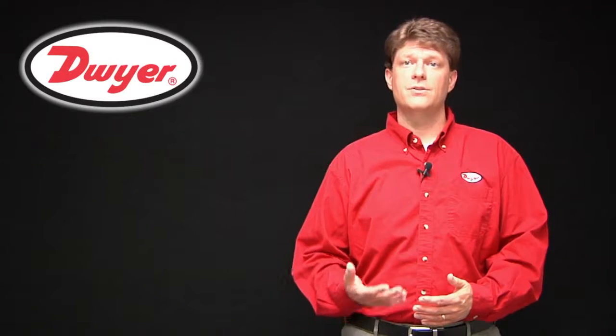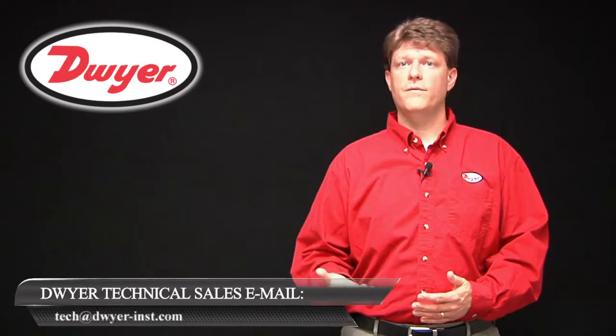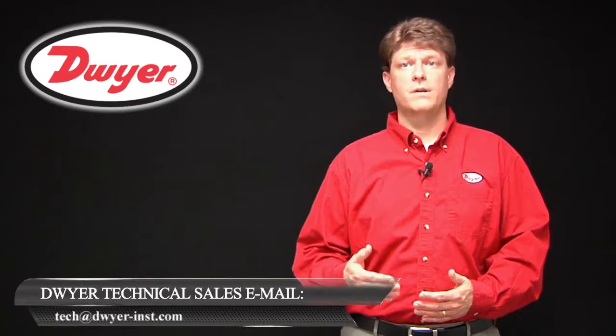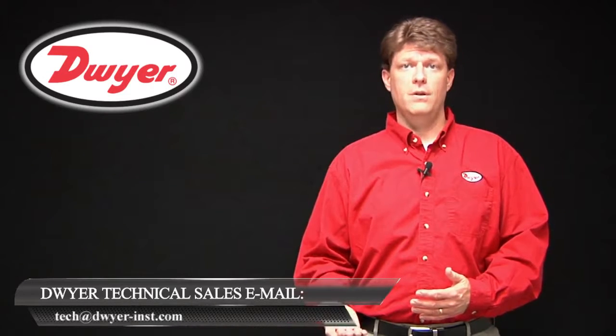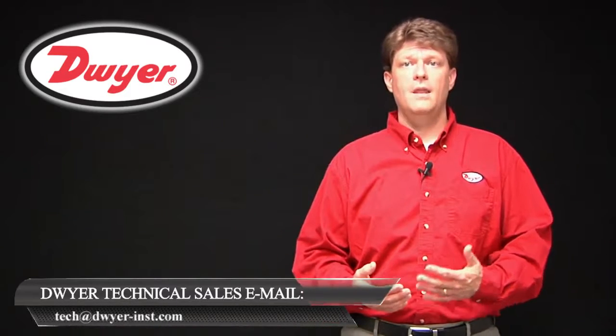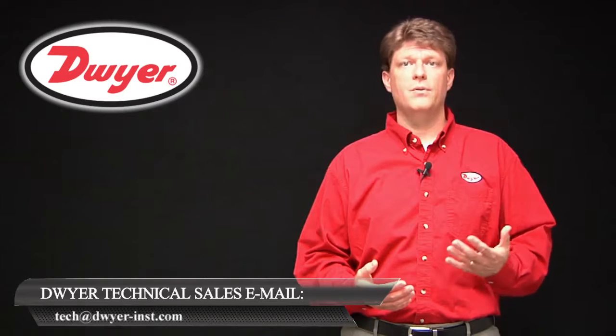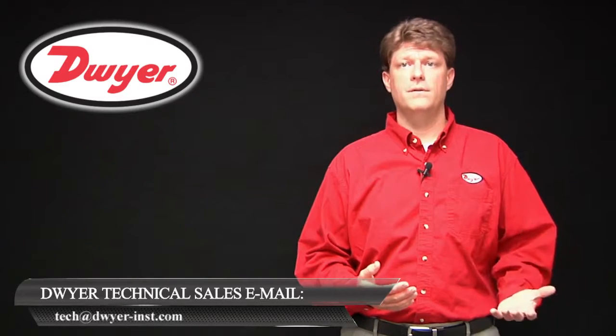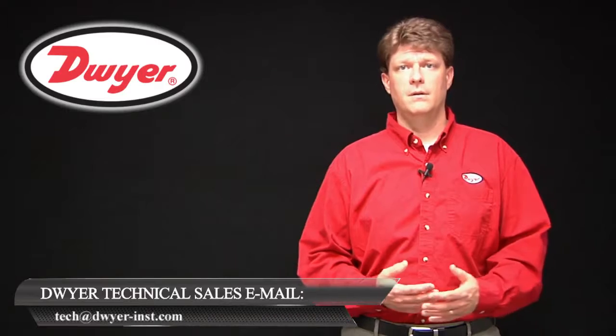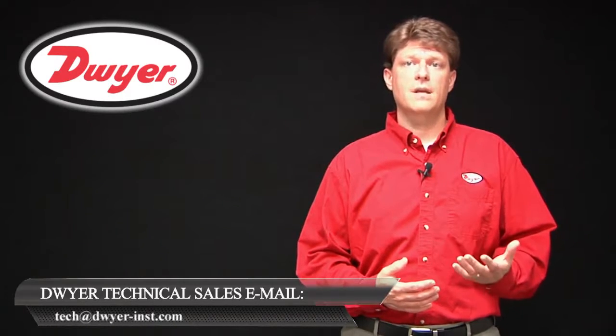Now that the calculations are complete, just tell Dwyer what the full scale range that you want is, for example, 3000, the units, for example, feet per minute, and the flow correlation data, for example, 2000 feet per minute at 0.25 inches of water column velocity pressure. Please contact our technical sales department for more help if needed.